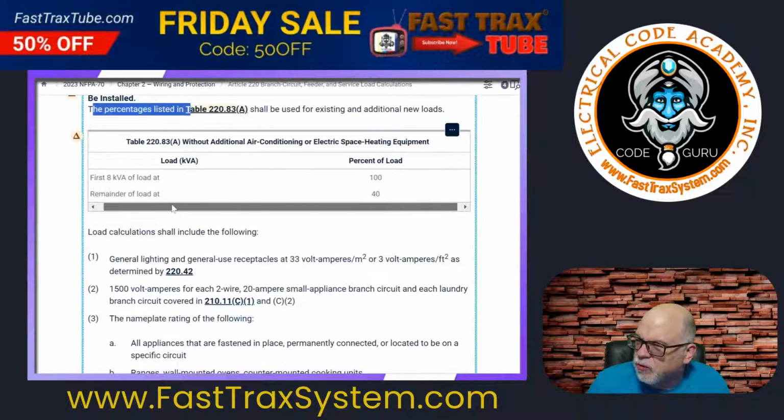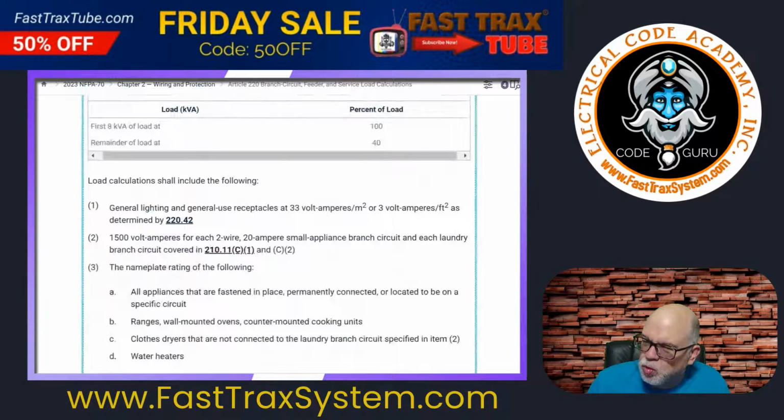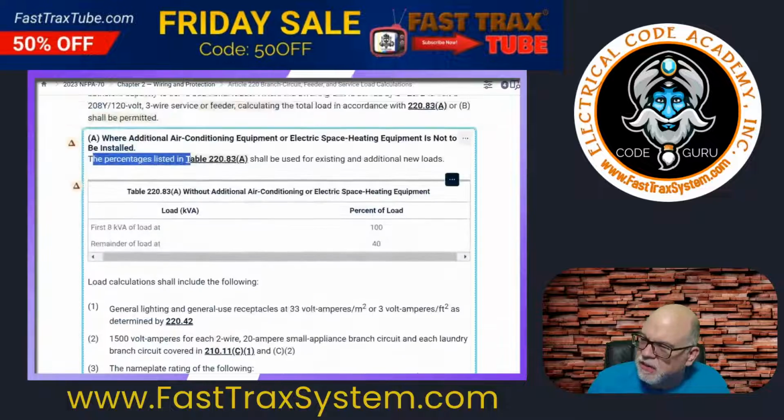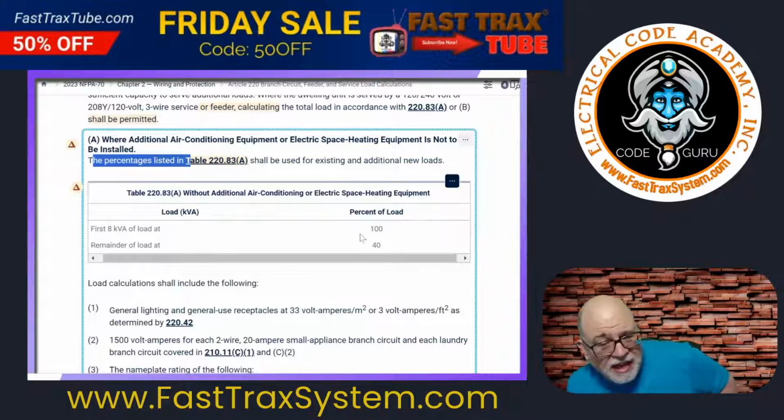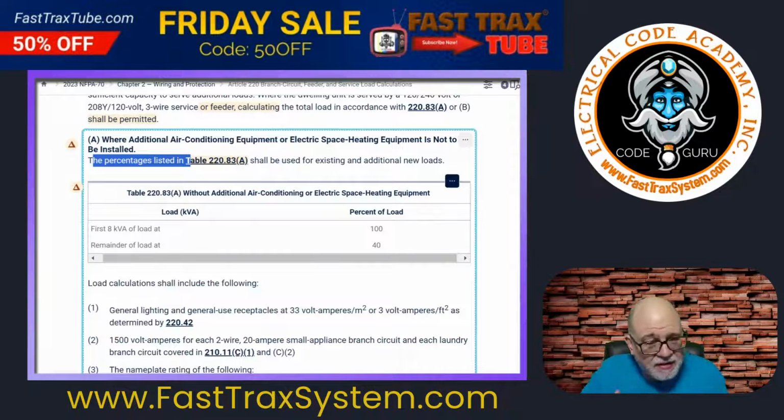I'll just scroll back and forth a little bit for you. You can see the whole thing. It says when you're going to apply these rules down here that we're going to look at, the first 8 kVA load at 100%. Right? So the first 8 kVA, you just take at 100%. Okay, so first 8,000 VA. Everything that you calculate or add up that's over that, then you're going to have a reduction. You're going to take it at 40%. Okay, so nice hefty allowance.